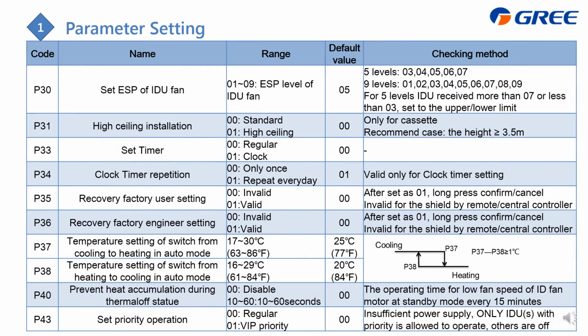Second page. This P31 is important, and also for the cassette type, if it is installed too high, we recommend less than 3.5 meters. If higher than this, we recommend setting it to high ceiling to increase the fan RPM.